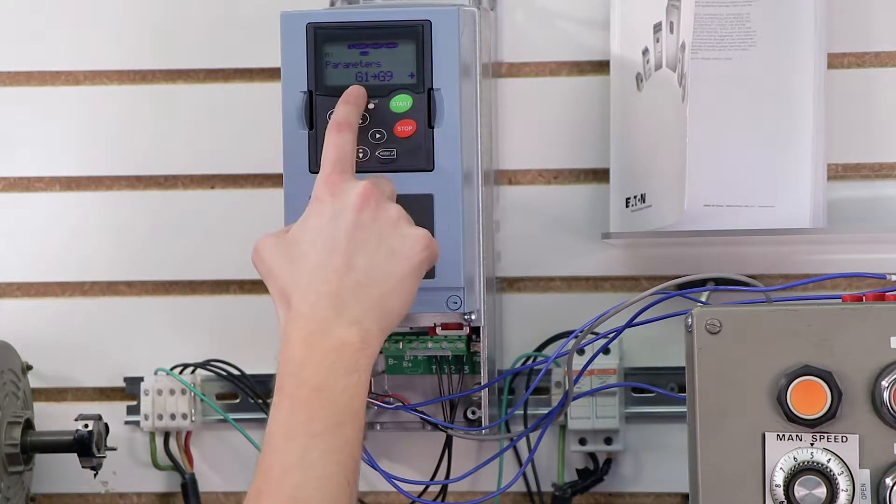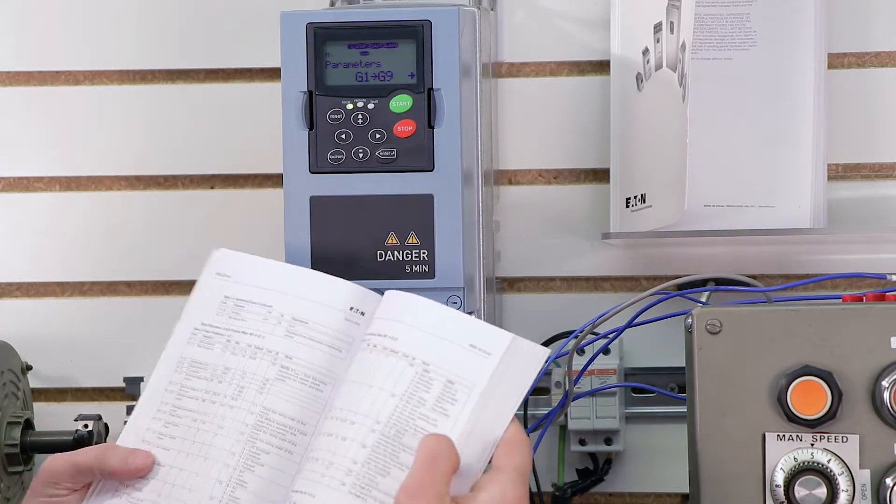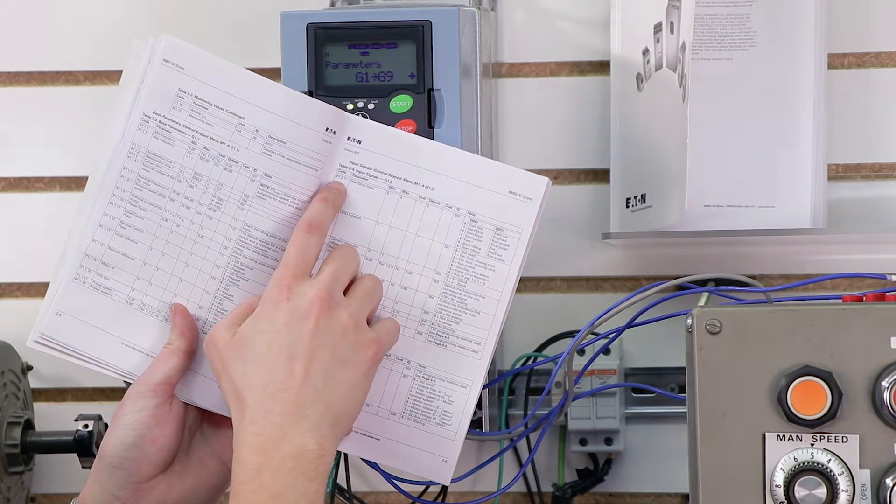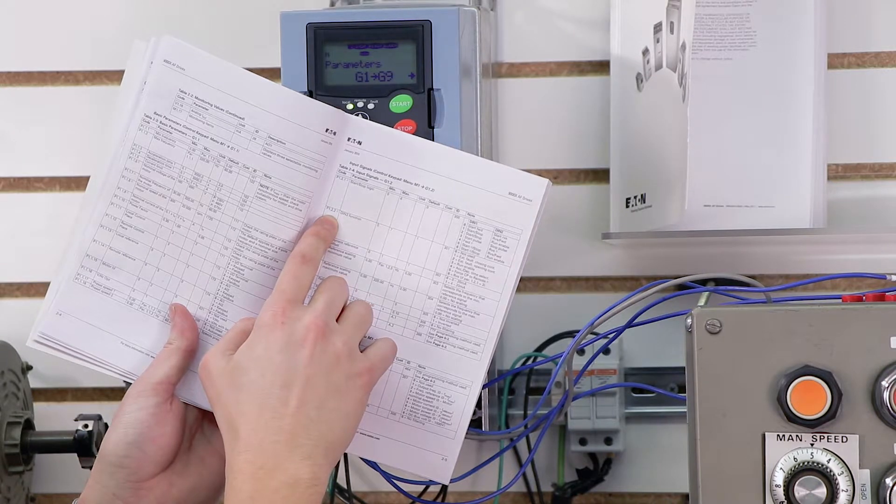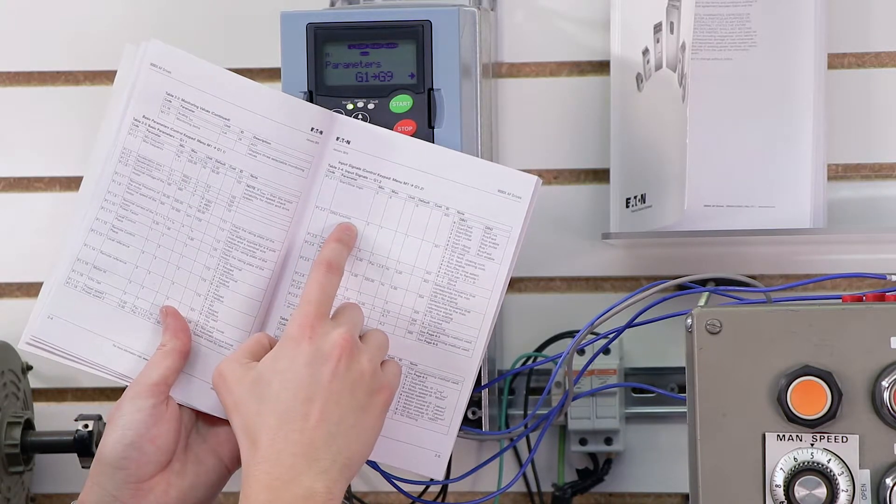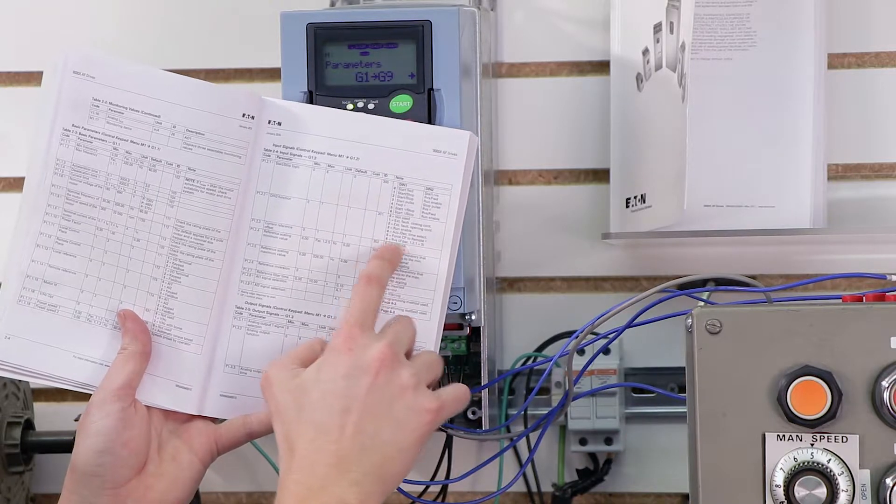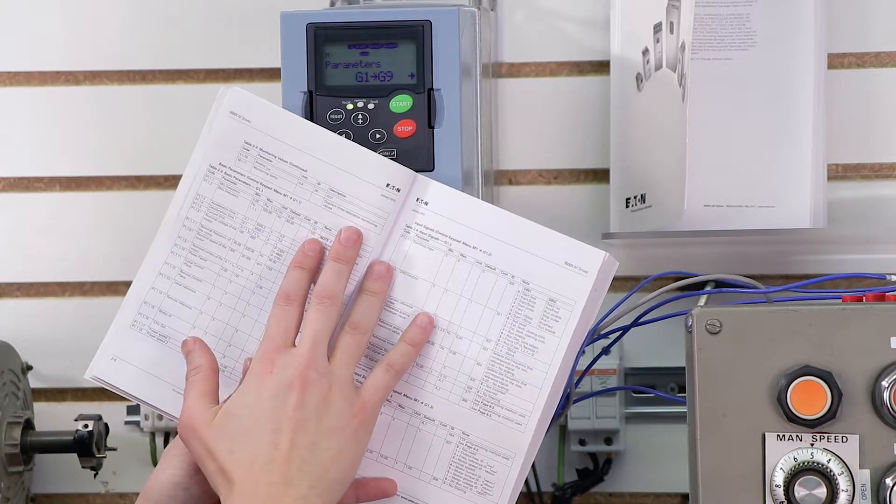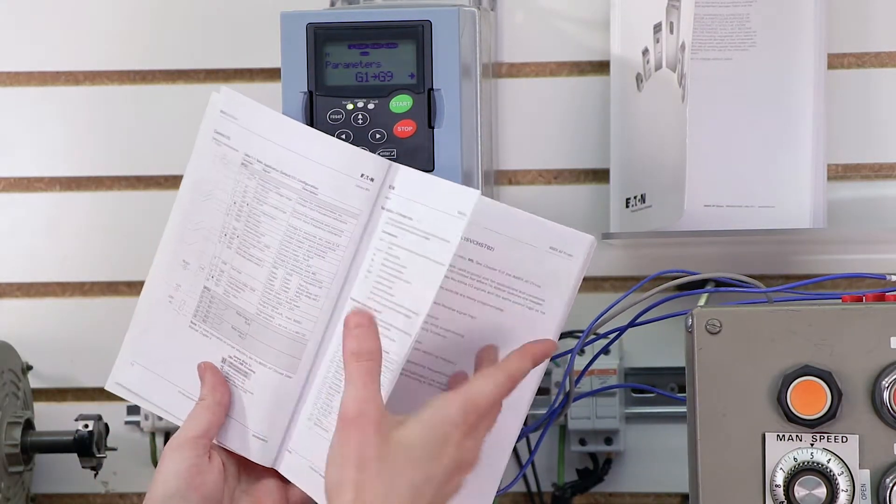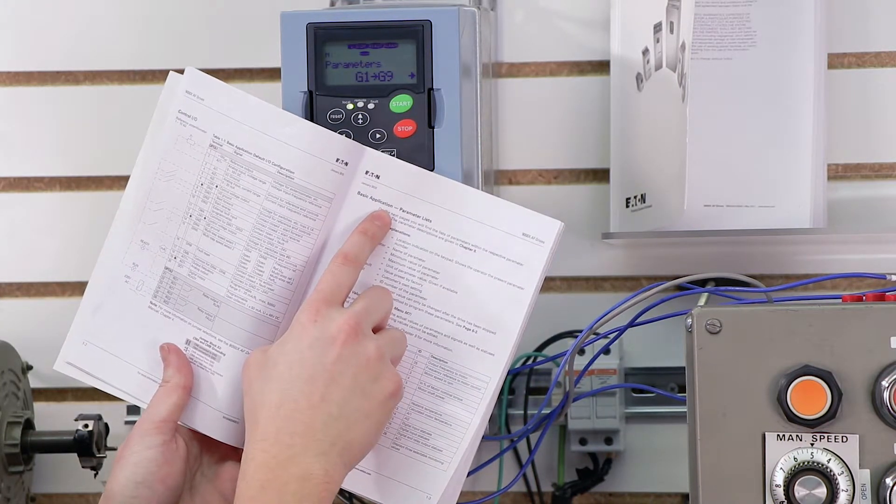And we're looking for parameters G1 through G9. Now, if I pull out my manual again, let me show you which parameters we're going to be modifying here. We're going to be modifying parameters 1.2.1 and 1.2.2. These particular parameters are our start-stop logic, and our digital input 3 function, which is going to be our reverse, we're going to be setting that to reverse here, which is number 6. Now before it will let me actually change these parameters, if you recall in our previous video, we're actually on the generic or the basic application.